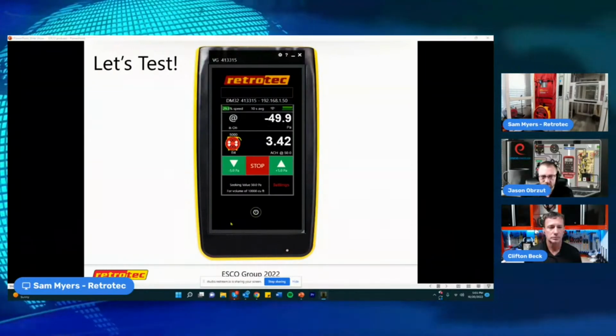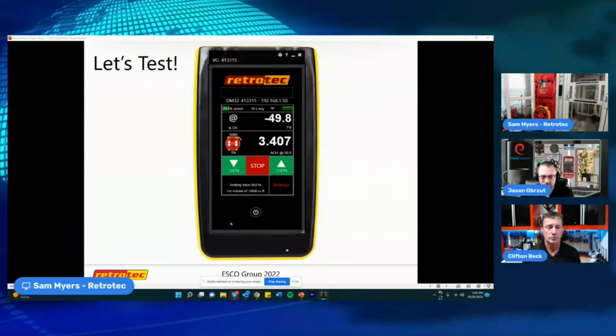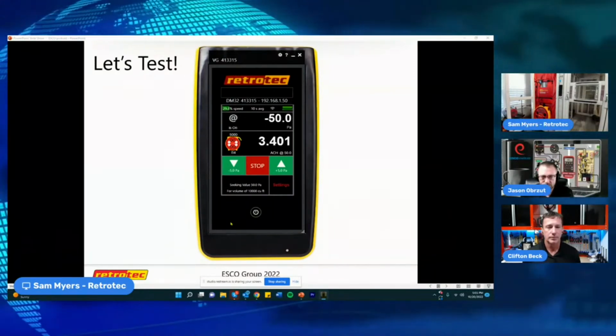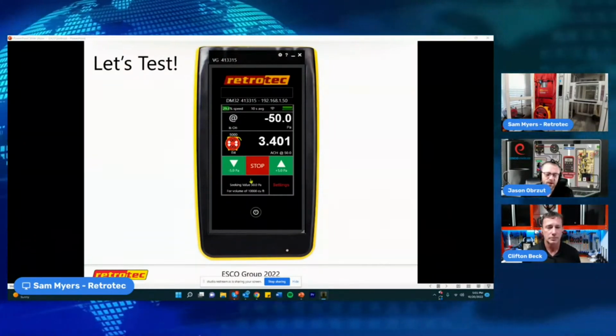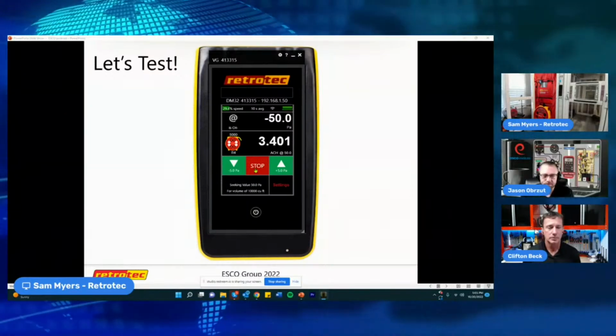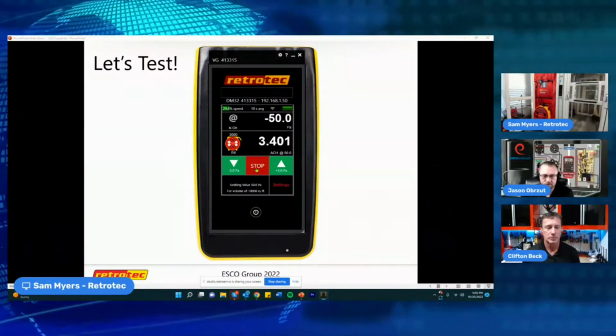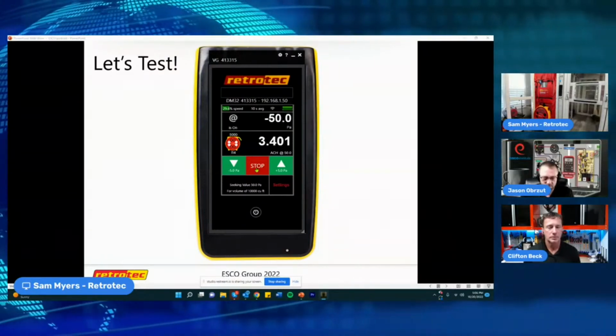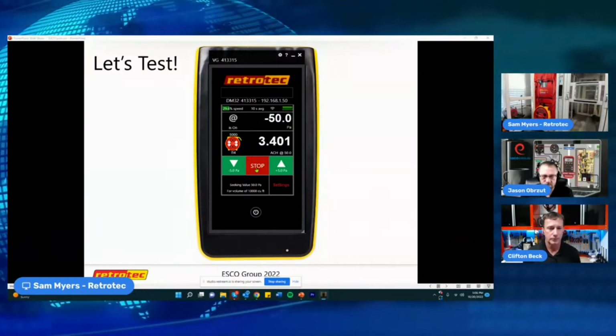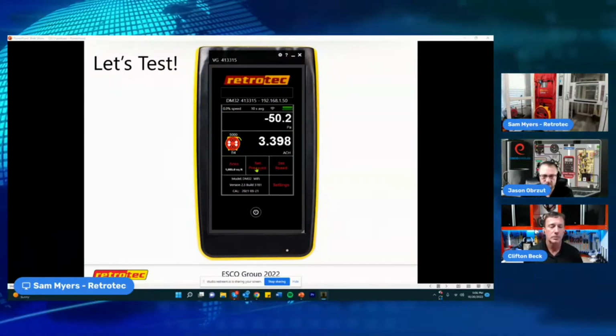So I'm getting 3.4 ACH 50 for my pretend house here that I'm testing. Sure. And by standard, that would be pretty tight. Yeah, it would. There's not a lot of codes out there that require less than 3. Usually it's within 5 or 6 or 7.